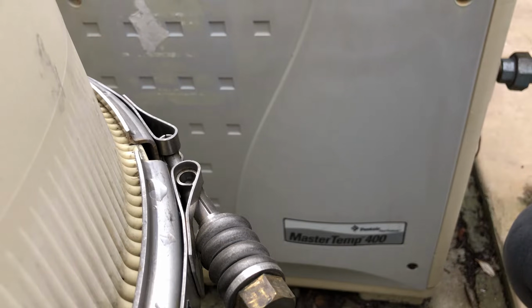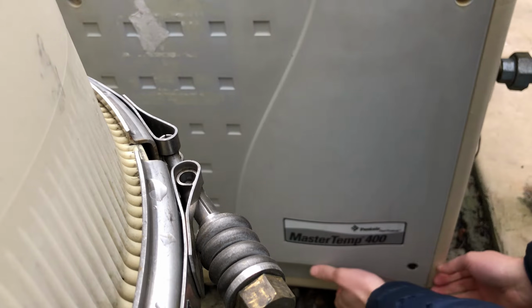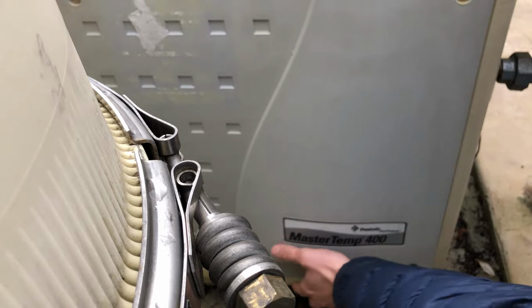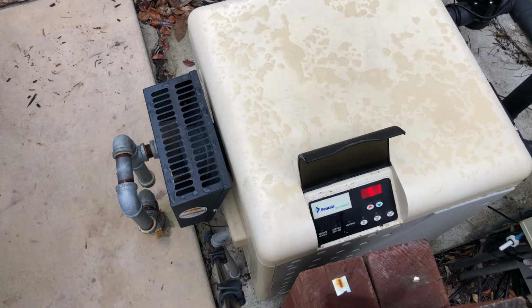It would say E05 for error code 05, which indicates something going on with the exhaust sensor. I'll post a link to the Pentair Master Temp 400 manual below. They have a really nice flow diagram for troubleshooting, and it'll ask you questions: did it fire, yes; did it shut back off, yes.